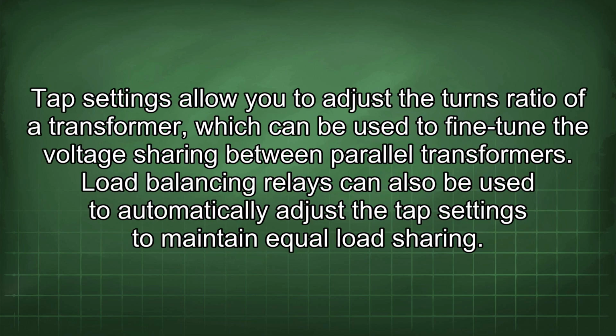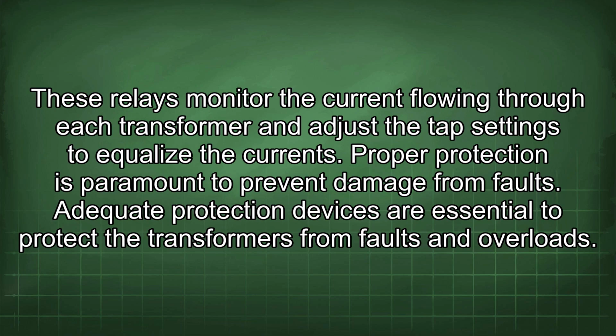Tap settings allow you to adjust the turns ratio of a transformer, which can be used to fine-tune the voltage sharing between parallel transformers. Load balancing relays can also be used to automatically adjust the tap settings to maintain equal load sharing. These relays monitor the current flowing through each transformer and adjust the tap settings to equalize the currents.